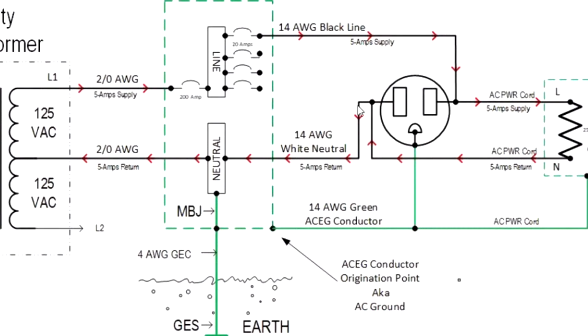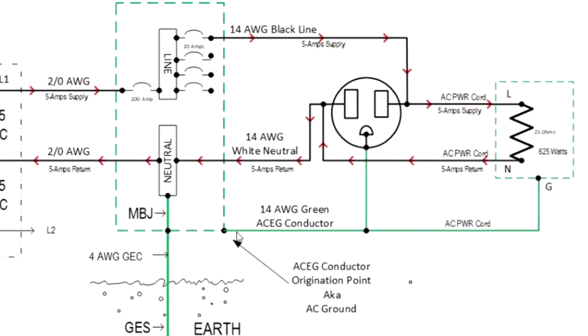For distribution, we'll start with the ground wire, and that's the green wire that goes with your AC branch circuit. It'll go right to the wall socket. You'll also have the white neutral conductor going to the socket, and then up here at the top, the line conductor, which is called hot, on a 20 amp breaker. What I'm showing out here on the end is a device plugged in. We can see the power cord with its 3 representative conductors. Take note that this is a 3-wire system, so the ground and neutral have no bond. The ground circuit has no electrical connection with the AC circuit at all. It's completely isolated.